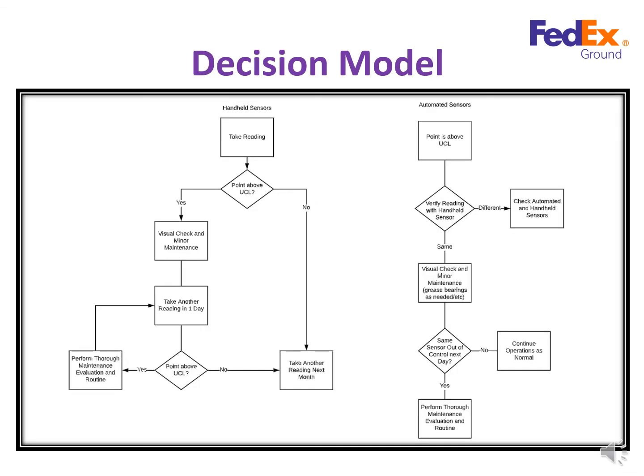Our decision tree is broken up into 2 branches that break off further based on the answers to the questions in each diamond box. For each scanner, if a point is above the upper control limit, we perform a visual check to see if any minor maintenance needs to be conducted or if any evidence of failure is present. If maintenance is performed, we then wait until the next day and record another reading. If that point is above the upper control limit once again, we then perform more extensive maintenance.